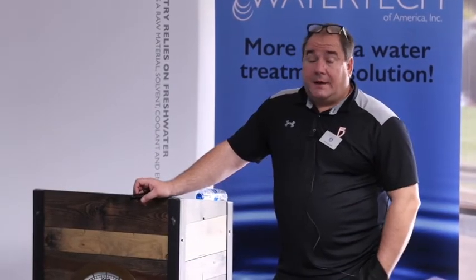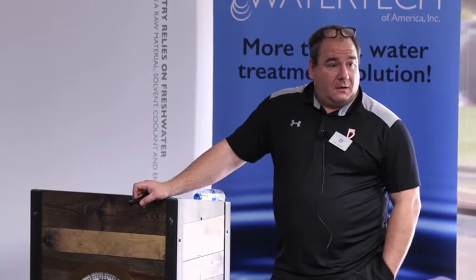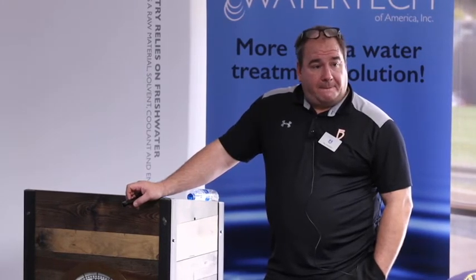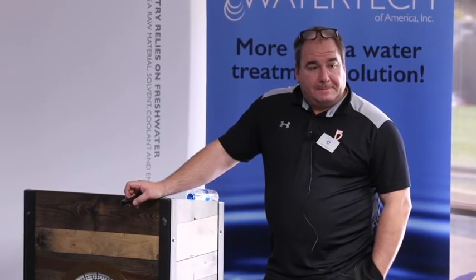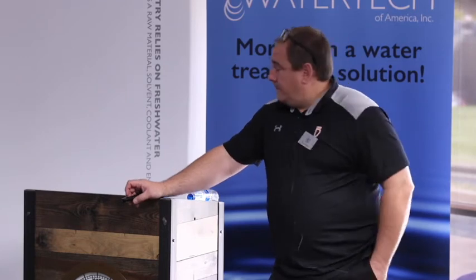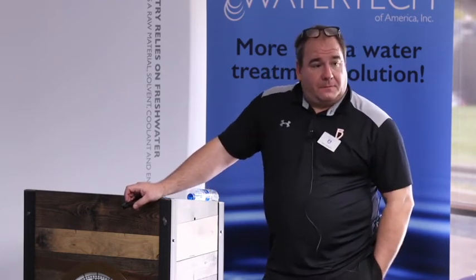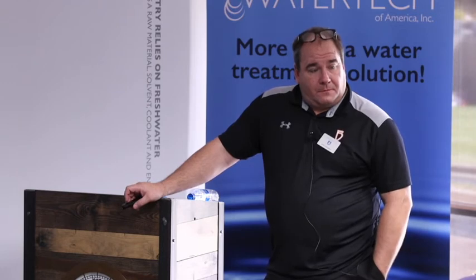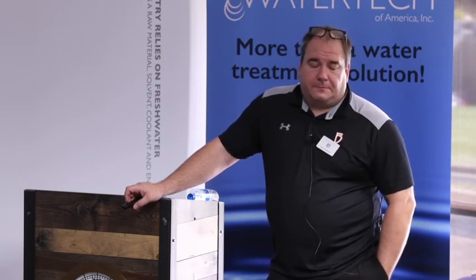Any questions, guys? I noticed that when our process one or process two hot water heat exchangers get a hole in it, the conductivity in my boiler shoots up. Yep. And then it leads me right to those, and I take the conductivity reading straight from those, and I can tell which one is actually leaking.